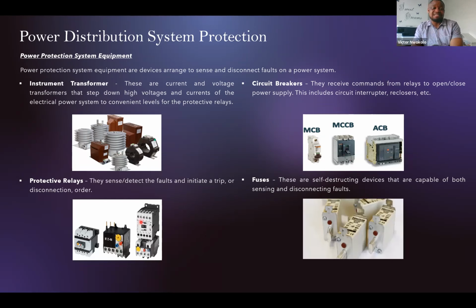The two protection devices there are protective relays and fuses. Instrument transformers and circuit breakers are considered other equipment that are used in a protection scheme. A quick definition of an instrument transformer: it is current transformers and voltage transformers. These are the elements of a protection scheme that read the current and voltages of the power system and pass that information to the protection relays.